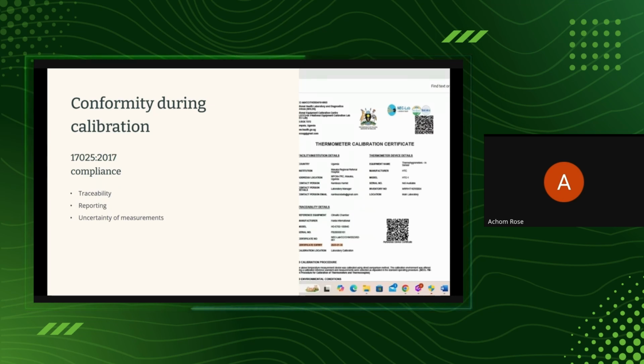The method you're using to calibrate these autoclaves has to be acceptable. If it is an internal method that you developed yourself, then you have to validate it and show that, although it is your own method, you are getting the same results as whoever is using another method. Then the reporting should be a standard reporting.